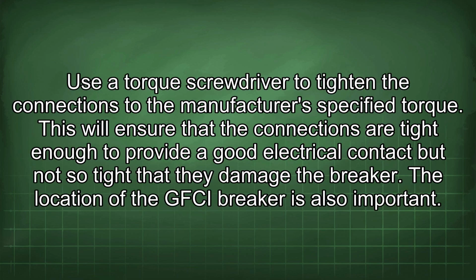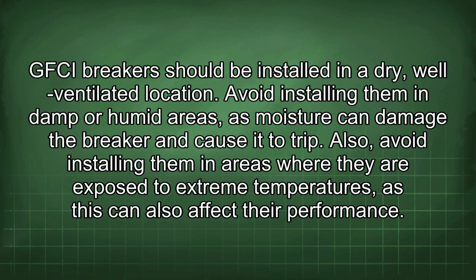Use a torque screwdriver to tighten the connections to the manufacturer's specified torque. This will ensure that the connections are tight enough to provide a good electrical contact, but not so tight that they damage the breaker. The location of the GFCI breaker is also important. GFCI breakers should be installed in a dry, well-ventilated location. Avoid installing them in damp or humid areas, as moisture can damage the breaker and cause it to trip. Also, avoid installing them in areas where they are exposed to extreme temperatures, as this can also affect their performance.